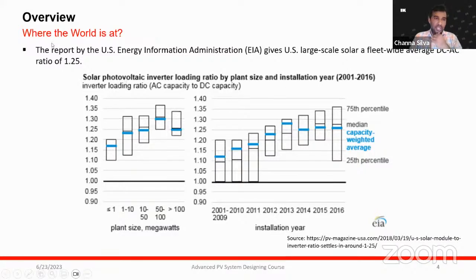The US Energy Information Administration published information for scales less than 1 megawatt up to 100 megawatts, showing how they do AC to DC capacity oversizing, meaning array oversizing. For less than 1 megawatt, they look at about 15% to 20% array oversizing - common for residential and medium scale, based on inverter technical specifications, often 10 to 20%. For large scale, people approach close to 40%, typically around 30% to 40% array oversizing.